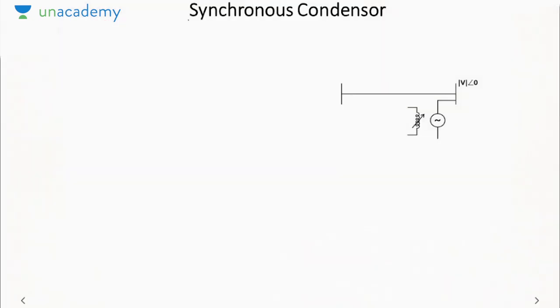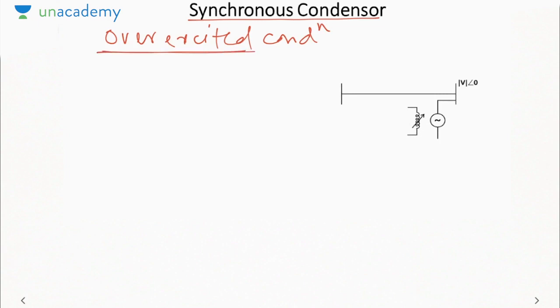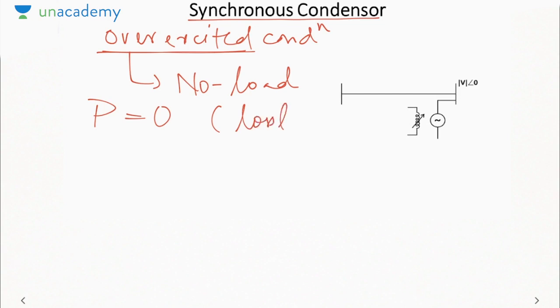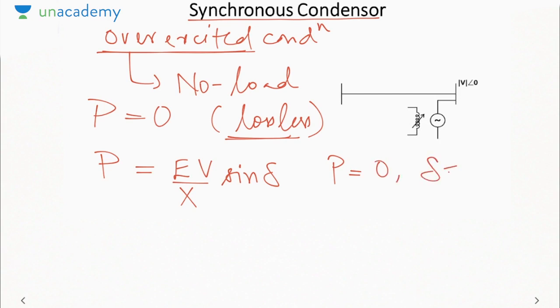So the first device that we study is the synchronous condenser or synchronous capacitor. That means it is a synchronous motor under overexcited condition. It is running at overexcited condition, but one more condition should be used here, that it is running at no load. No load means real power is 0. I am assuming a lossless machine. Practically real power cannot be 0 because it will consume some real power at least to supply the losses. So assuming real power is 0, we are assuming that the machine is lossless. Now real power is given as EV by X sine delta. So real power 0 implies that delta is 0.